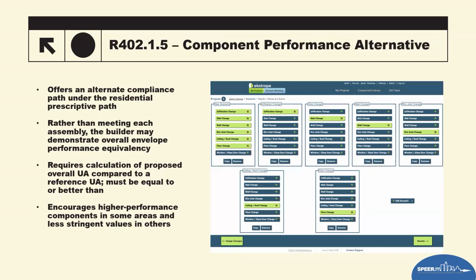This is introduced in the 2024. What that means is that instead of strictly satisfying each line item for walls, roofs, floors, and fenestrations, you can now model the actual assemblies, compute the total UA, and show whether the proposed UA meets compliance by comparing it to a reference UA. This allows for trade-offs, basically envelope shell trade-offs. It doesn't really include mechanicals. So for design teams, this means optimal cost and efficiency trade-offs by selecting components that better fit the flexibility of your building and construction.